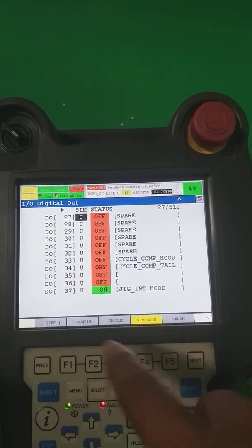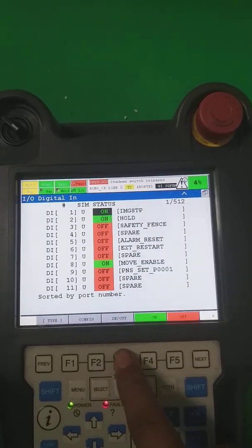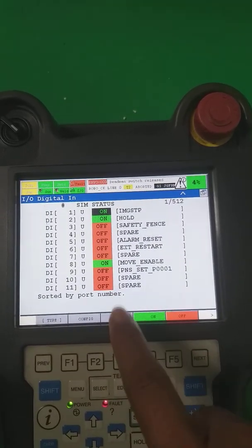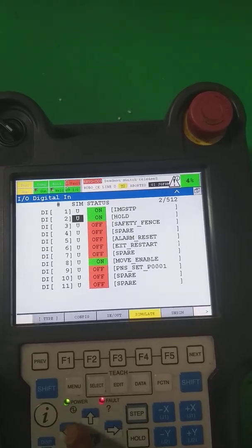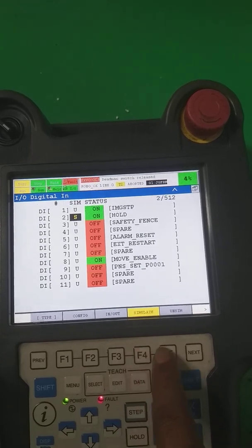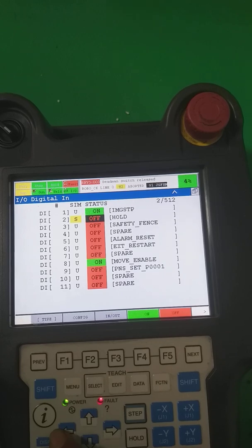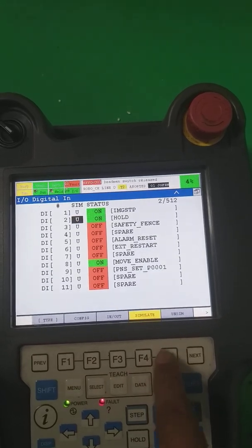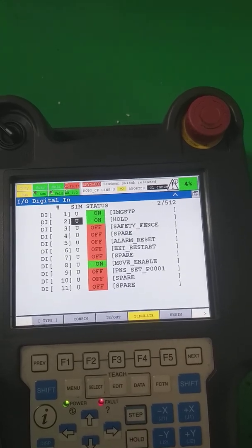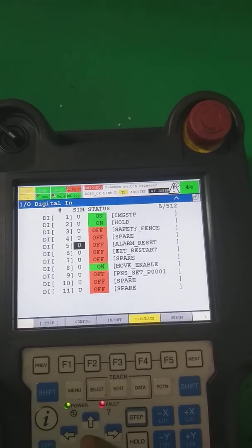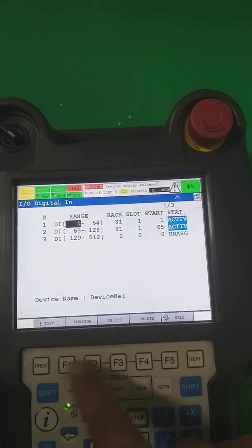Here you can also make it simulate, as I mentioned in the cell interface. When you simulate, one output will forcefully turn on. These are the inputs as well — you can simulate them forcefully if you are not able to receive from the field. However, never use simulate during auto trial because it can cause accidents. Use it only in prep and configuration.